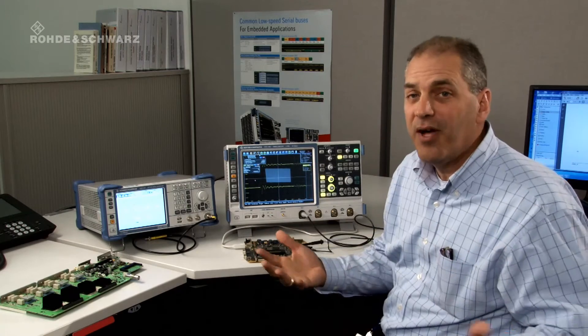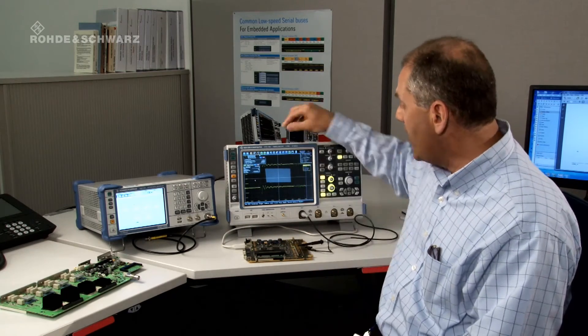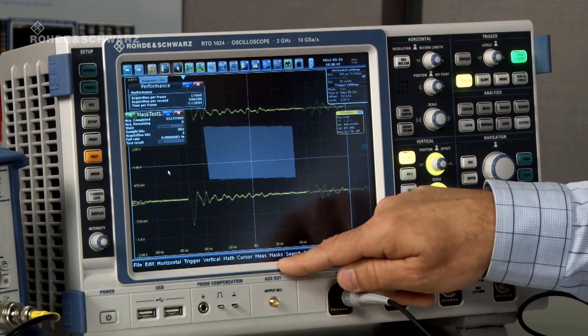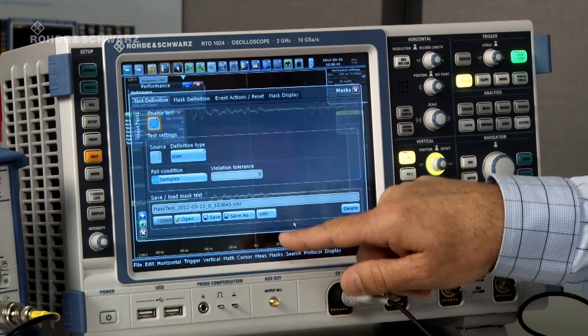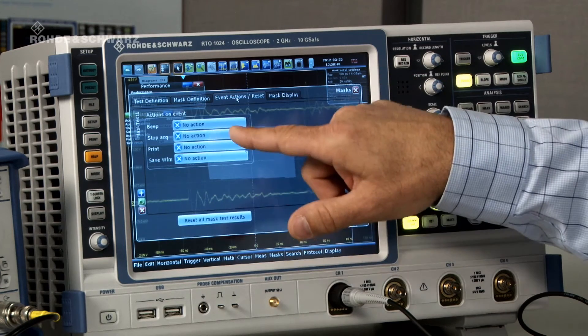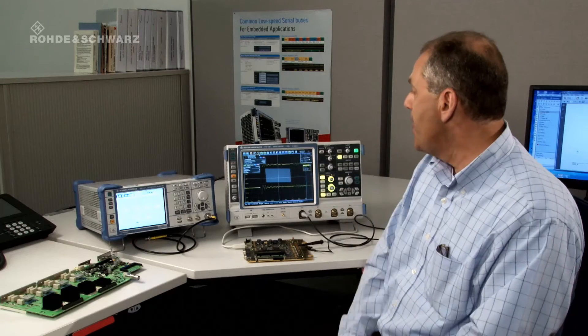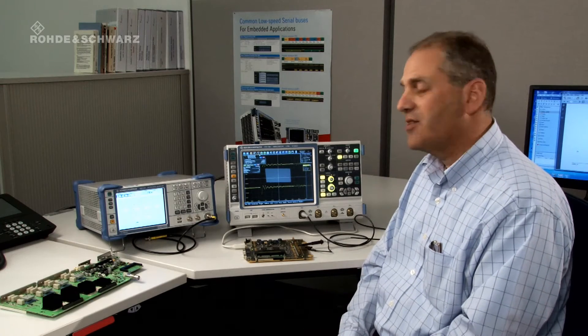Of course, no one would wait days to find an error so they probably wouldn't find the error. So let's go ahead and set this thing up to capture an error. And what I'm going to do is I'm going to tell the instrument to stop next time it finds an error. And so I'm going to go in event actions and say stop acquisition on violation. And we're going to wait just a few seconds to see what happens.